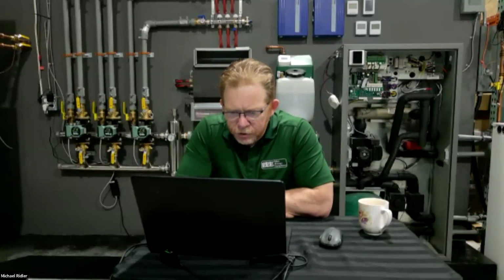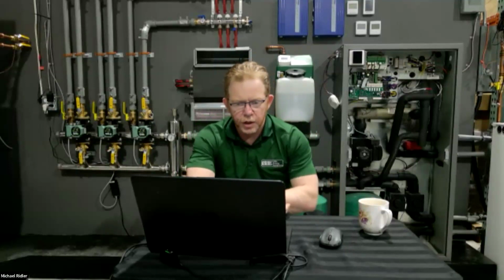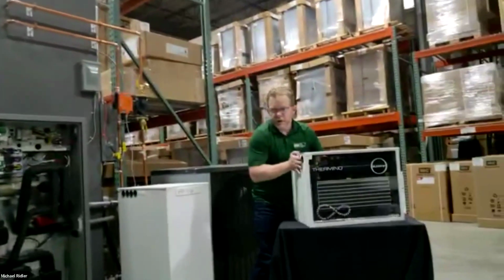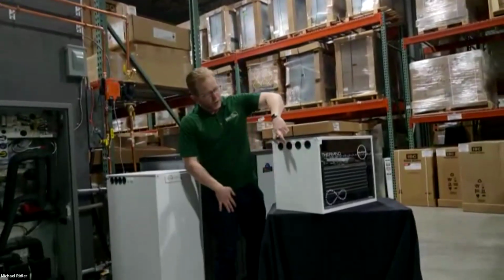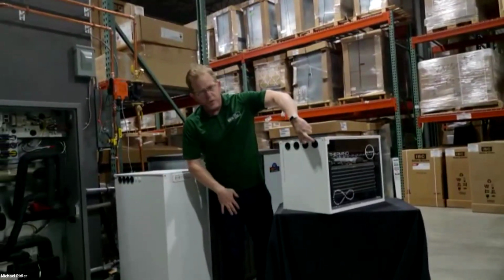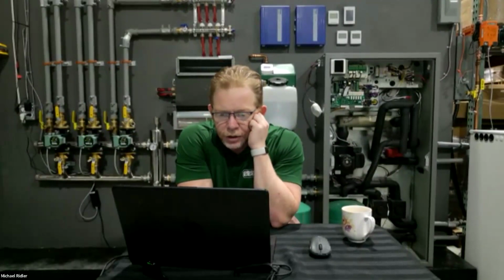Mason asks, do you know if manufacturers are providing piping diagrams for retrofits or upgrades to existing systems? Let me scroll over and show you mine. It's pretty simple—basically you just need charging ports and discharge ports. The number one thing I'll point out, which you probably saw in that photo, is they typically have a flat heat exchanger inside, sort of like a hydronic coil. In fact, it literally is a hydronic coil, and the pressure drop is really high.